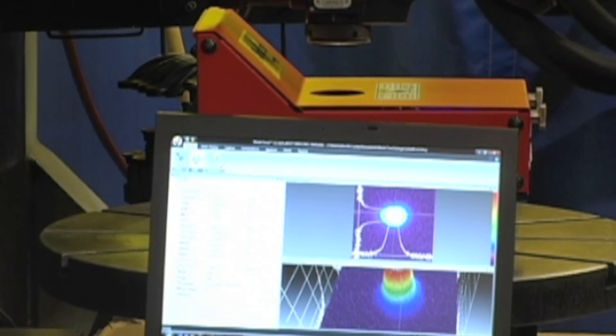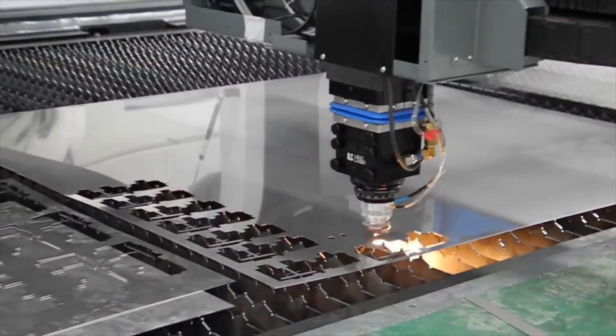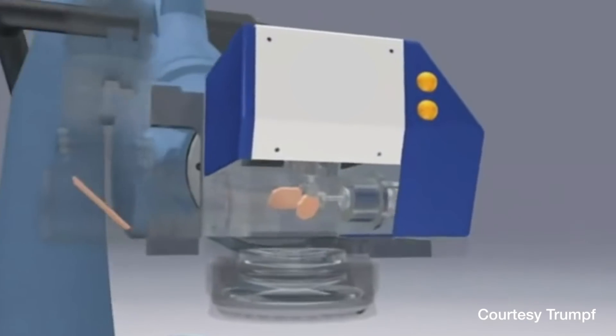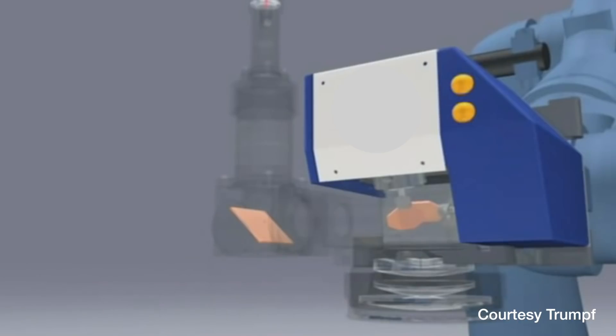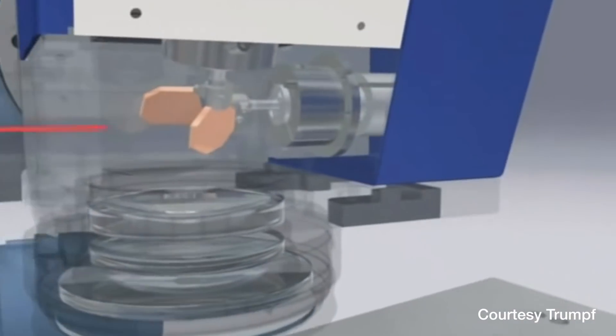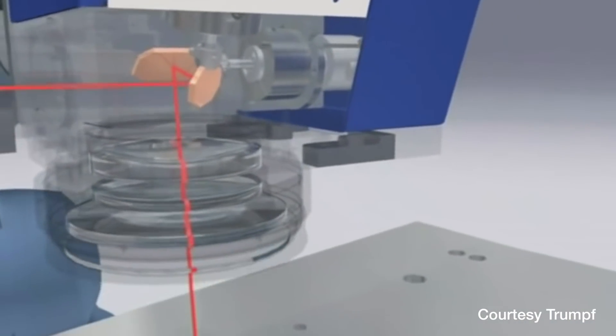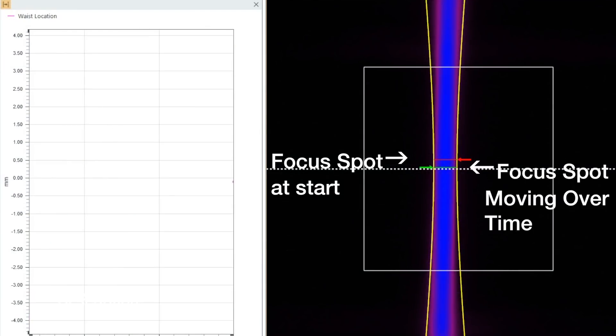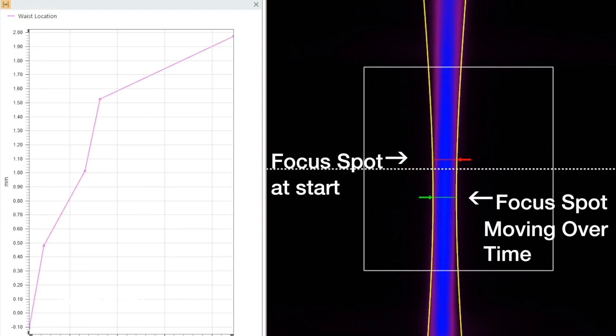Therefore, measuring your laser's performance is crucial to continued quality operations. The degradation of laser system components will ultimately result in a reduction in system efficiency. Laser power will likely decrease over time because laser optics and mirrors gradually absorb more laser light as they age or become contaminated. And because of the thermal effects that this absorption results in, the laser's optics will slightly change shape and the focused spot will experience changes in size or location with respect to the process, known as focus shift.